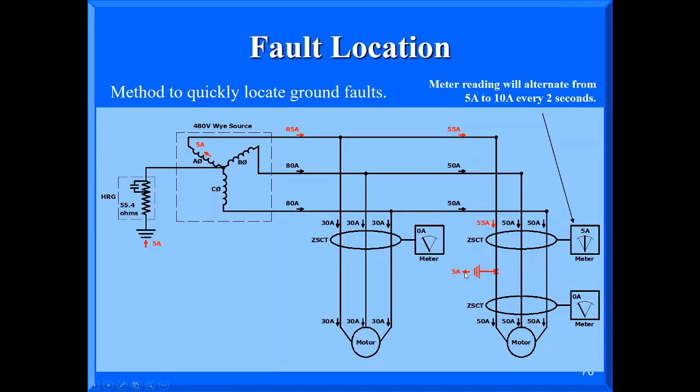I had a case in a brick plant that was ungrounded. I put in a portable system, and I went to the main switch gear, saw the ground fault. The way this building was set up, it went out to a telephone pole, and that fortunately came down, and they had two disconnects.